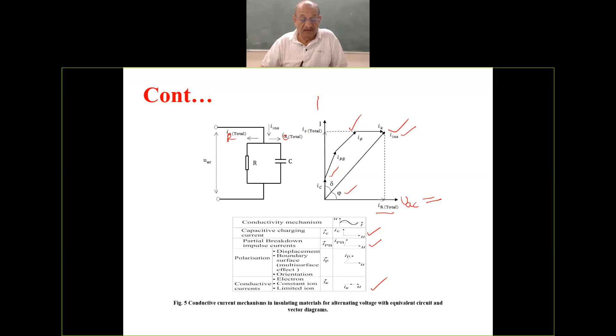So this delta angle actually determines the active power loss in the dielectric. We will analyze this active power loss in the dielectrics next time. Tan of delta is the measure of active power loss by reactive power loss. If you go back to this, tan of delta is the resistive current IR total divided by the reactive current, that is IC total. IR total divided by IC total gives you tan of delta. So tan of delta is a quotient, or a ratio, between the active and reactive power loss, and these are given in the phasor diagram in this way.